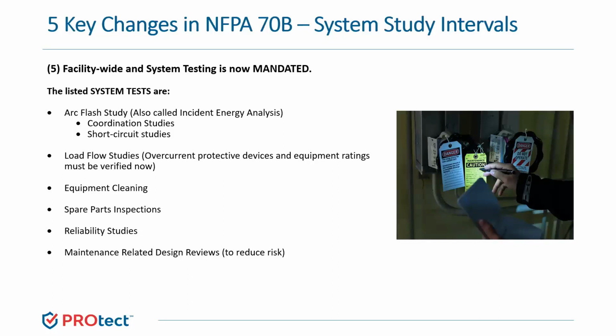You will be required to have infrared inspections completed as well as other inspection testing methods, as we noted above, such as insulation resistance testing, inverse time trip testing, instantaneous overcurrent trip testing, and of course the arc flash requirements we just discussed.